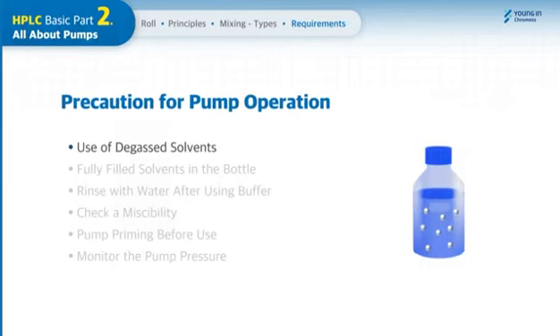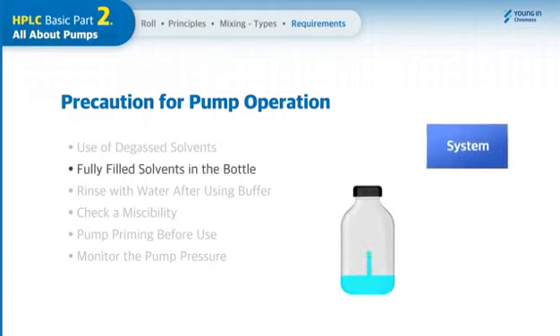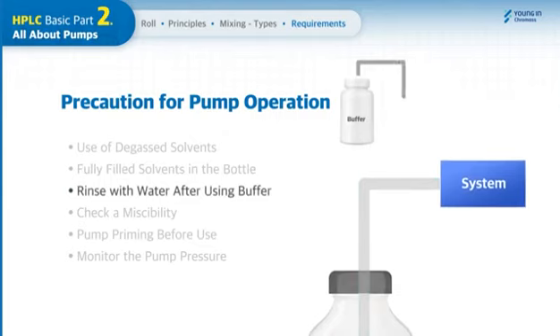If you use the solvents with air bubbles, the flow fluctuation will occur, so does the poor repeatability. So, all solvents used for HPLC must be degassed. When the use of almost use-up solvents, the solvent will be empty sooner or later, and the air bubbles can be introduced to the HPLC system. So, you need to check whether the solvent is filled in the bottle before use. With the use of a buffer, there might be salts remaining on the surface where the solvents flow. So, you have to rinse fully the system with water after using a buffer.